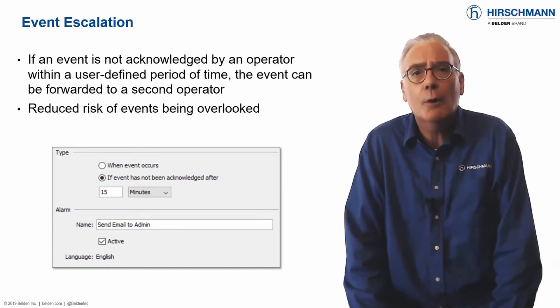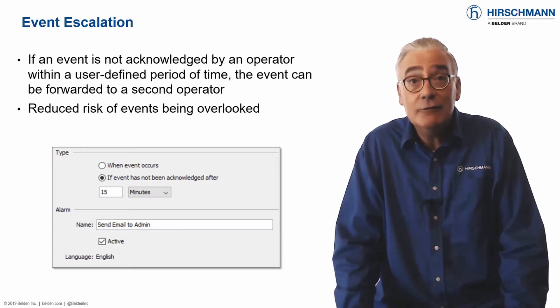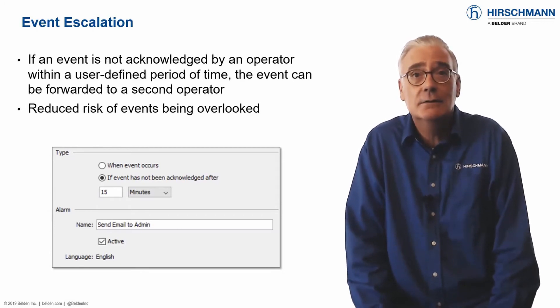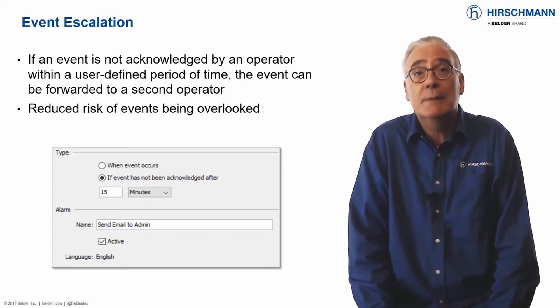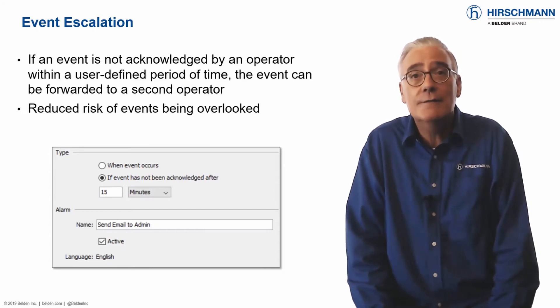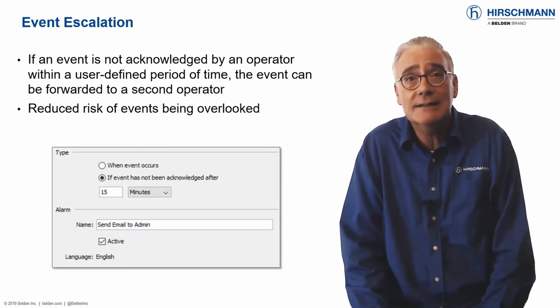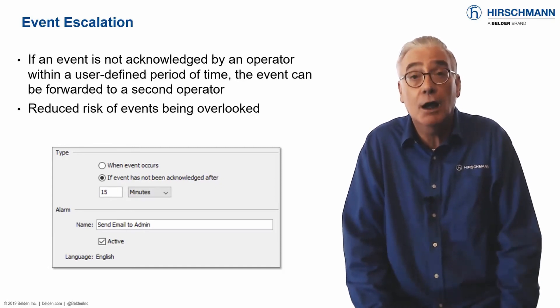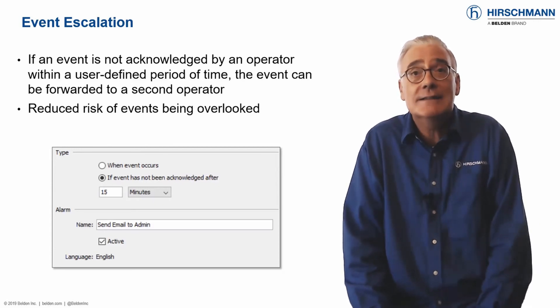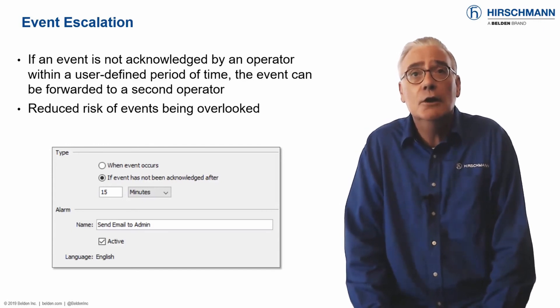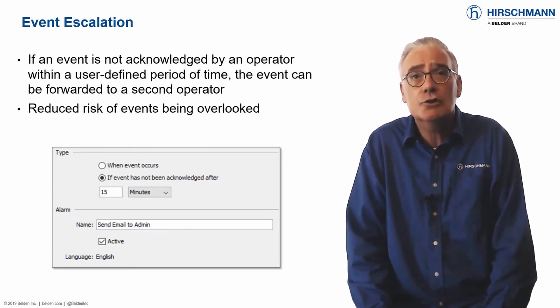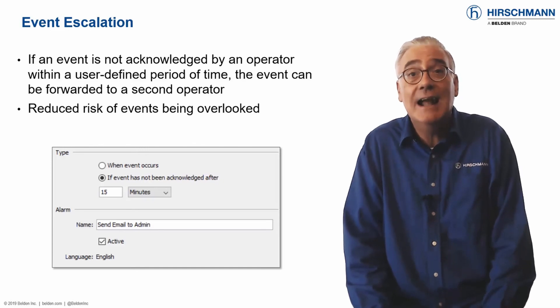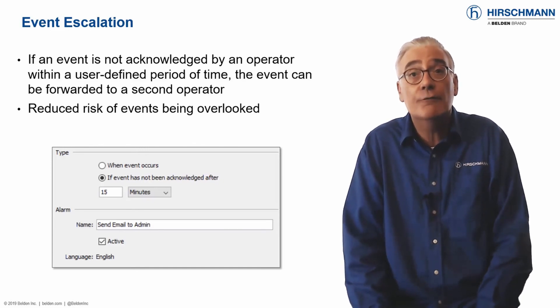In a perfect world, your network operators would see and acknowledge every event. In reality, sometimes the operators will be focused on other tasks and events will get missed. Industrial HiVision offers a simple function to mitigate this problem. Unacknowledged events can be redirected to an alternative operator or escalated to you. You can define the acknowledgement timeout period per alarm — for example, the higher the event severity, the shorter the acknowledgement period. You can also define how each event should be escalated. Event escalation reduces the chances of events being missed and helps you and your colleagues to maintain awareness of the network status.